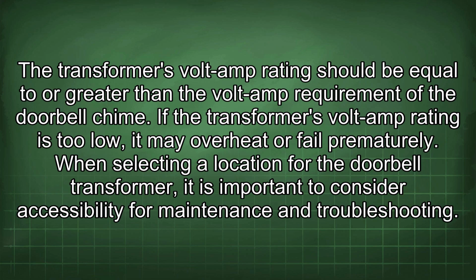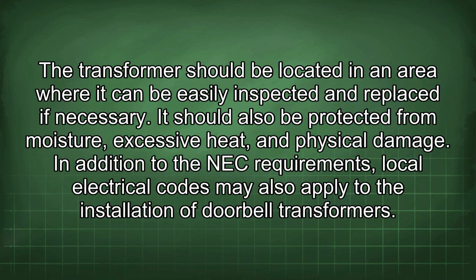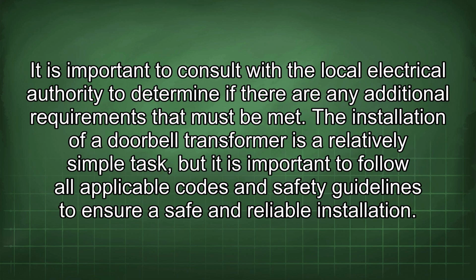When selecting a location for the doorbell transformer, it is important to consider accessibility for maintenance and troubleshooting. The transformer should be located in an area where it can be easily inspected and replaced if necessary. It should also be protected from moisture, excessive heat, and physical damage. In addition to the NEC requirements, local electrical codes may also apply to the installation of doorbell transformers.